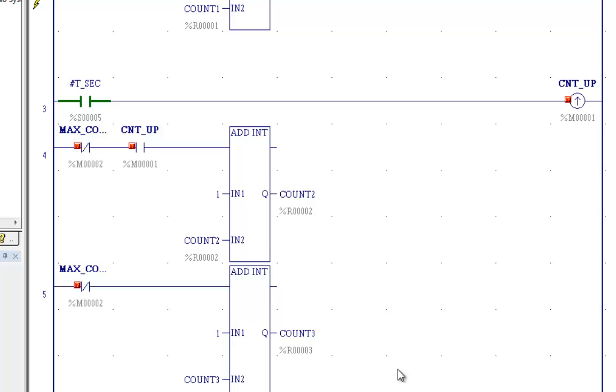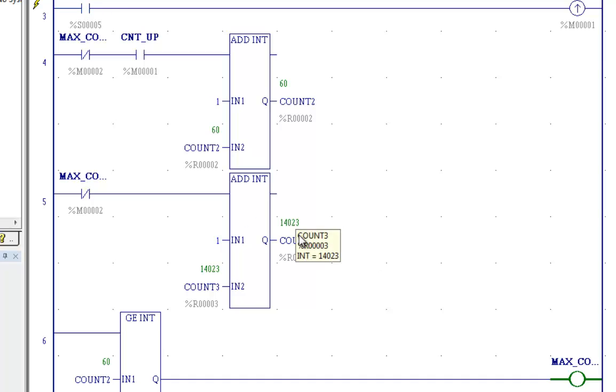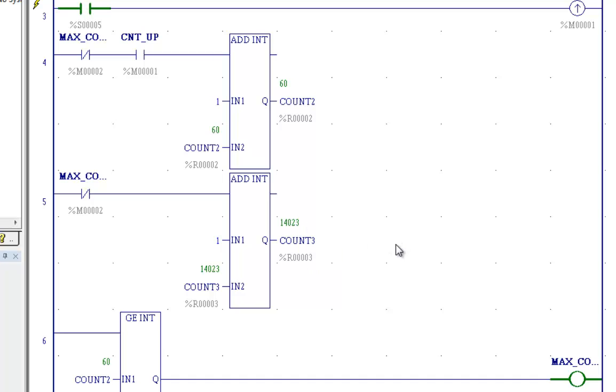Now I've got another counter here that will increment every scan. So over the 60 seconds that we'll be counting, you'll see I should come up with looks like about 14,000, about 14,000 counts. And if I do the math on that, 14,000 divided by 60, that works out to an average scan time of about 4.3 milliseconds.